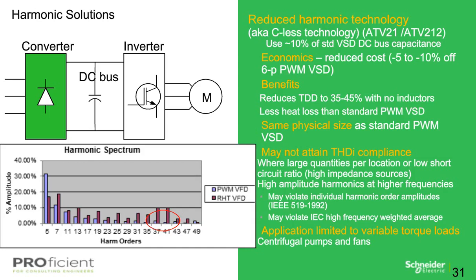So as mentioned, great lead into our next topic, which is reduced harmonic technology, which uses less capacitance in the DC bus to reduce the overall percent THDI. The total harmonic distortion levels are in the range of 35 to 45% THDI, similar to adding inductors to a 6-pulse VFD. The DC capacitors are replaced with new DC caps to handle the majority of the voltage cycling for extended product life cycle, which adds no heat losses to the VFD.